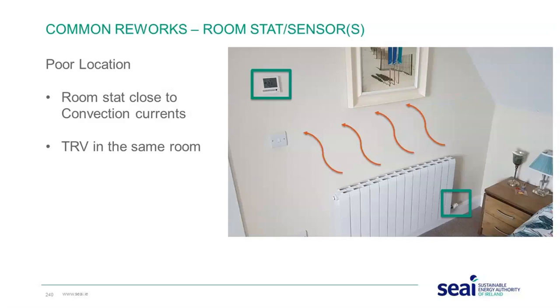So two thermostats will work against each other. If the TRV is set too low and the room stat is set to high, the room stat is not going to turn off the rest of the space heating. So every other radiator is there. So we ask, in the case of a room stat, please do not fit a TRV in the same room.